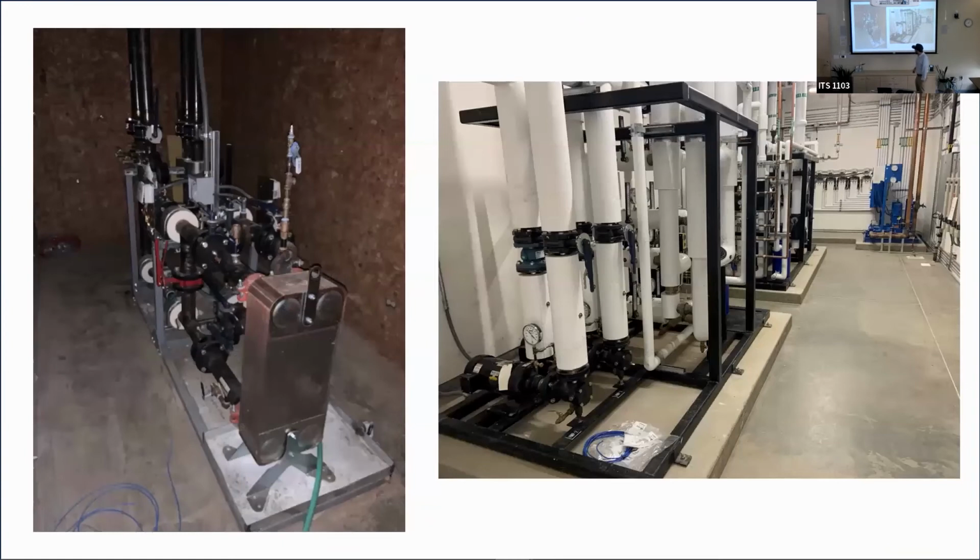And then at the building level, the heat exchangers, this is showing an existing building that had a steam heat exchanger that came out. It was getting hot water. The hydronic system in the building was being heated by steam with a large shell and tube heat exchanger. That's been replaced now with a brazed plate heat exchanger here that's taking the loop low temperature hot water, we call it, and heating the building hot water.